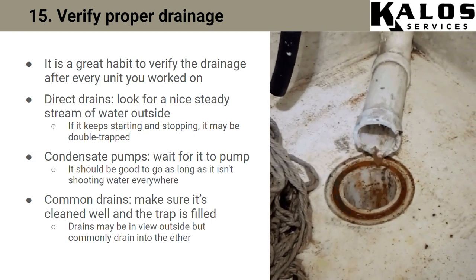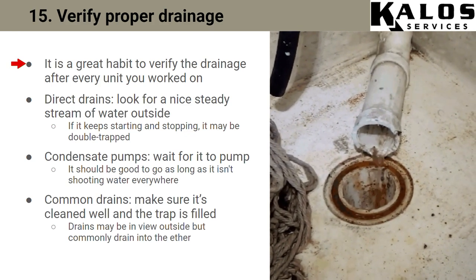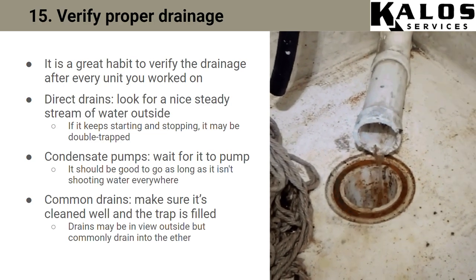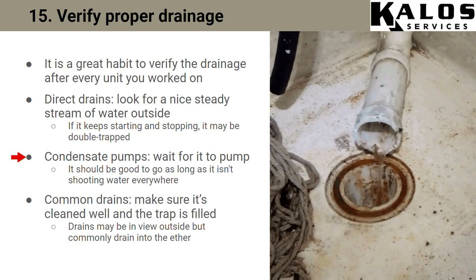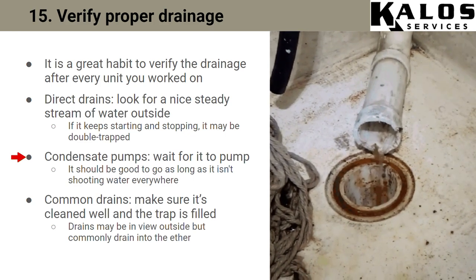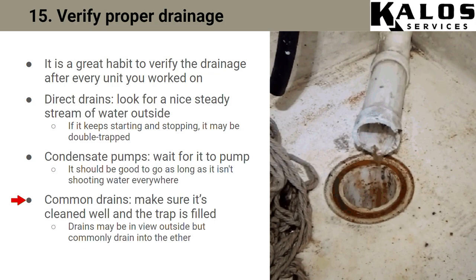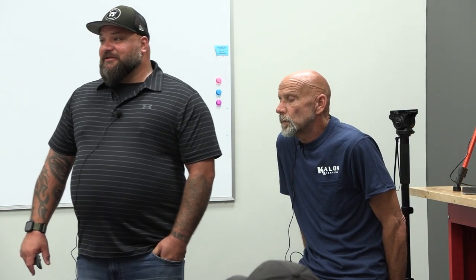Once panels are back on, go back to verifying drainage. If it's a direct drain, go outside and verify a steady stream — not starting and stopping, not barely dripping. For a condensate pump, see it pump and make sure it doesn't spray water everywhere. The common drain you better have cleaned thoroughly, because problems with common drains will come back to bite you and you'll never even know because it drains out of sight.